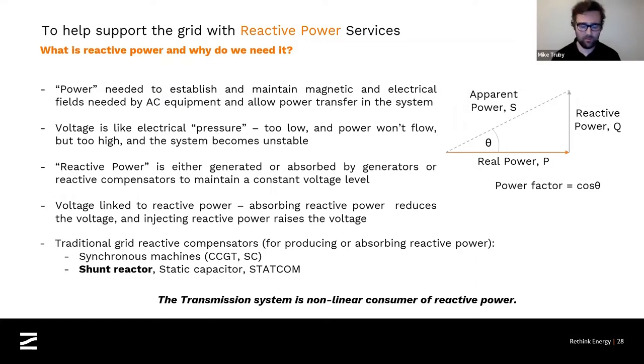The really important thing to understand is that the transmission system inherently, what it's doing with reactive power throughout the day is changing. As loads come on and offline, as industrial sites start up, as transformers change what they're doing, we are seeing that fluctuating and we're seeing the voltage fluctuating. And we need to be able to manage that as a network in real time.